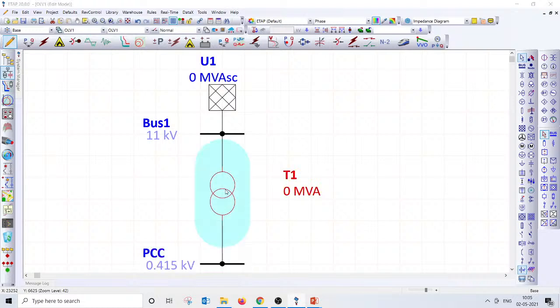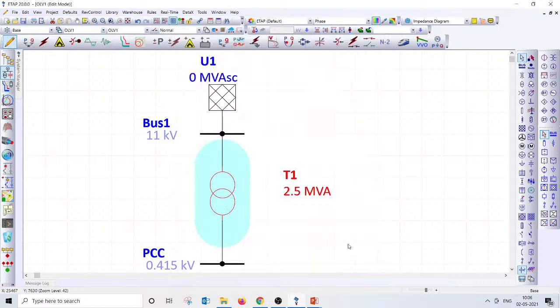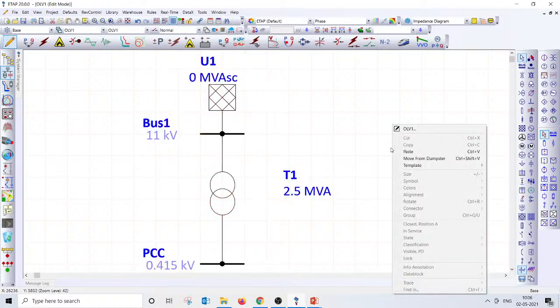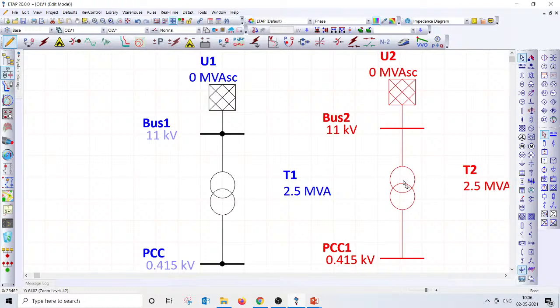Let's try to understand more why we should limit the transformer rating to 2.5 MVA. 2.5 MVA is really not a constraint, but we will see what the factors are which are pushing us more or less close to 2.5 MVA, right? Even 3.5 MVA transformers are available at 415 volts, but we can understand from one or two scenarios. If I am increasing this transformer to, for example, say 10 MVA, right? So that probably answers the question.